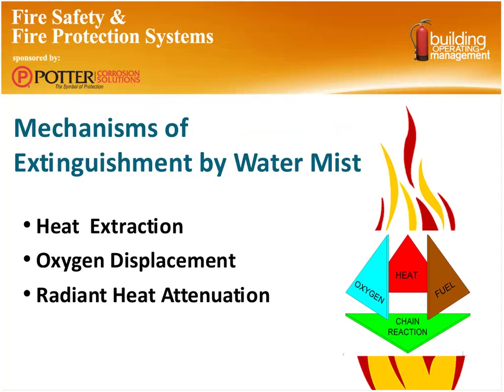So in recap, again, the mechanisms by which fine water mist actually stops a fire: heat extraction, a little bit of oxygen displacement, which is a little bit different than a traditional sprinkler system, and radiant heat attenuation. And because the droplets of a traditional sprinkler system fall out of suspension rapidly, typically they don't do a very good job of attenuating heat.